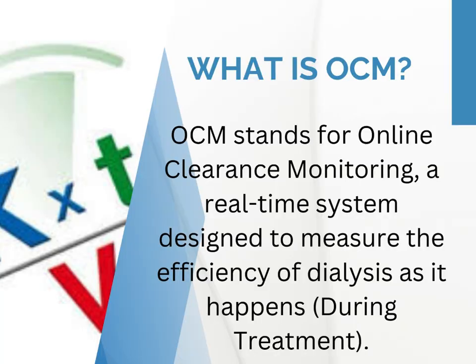So what exactly is OCM? OCM stands for Online Clearance Monitoring. It's a real-time system that checks how well dialysis is working during the treatment. Think of it as a fitness tracker, but instead of counting steps and calories, it monitors how effectively we are clearing toxins from the blood. No more waiting for post-dialysis blood tests — this gives us live data to act on.